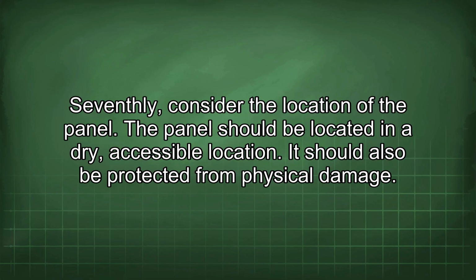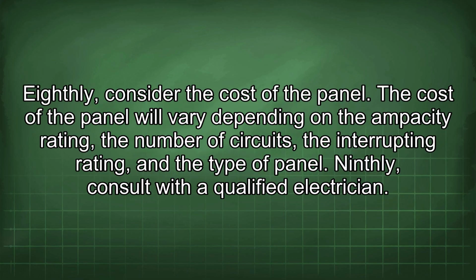Seventhly, consider the location of the panel. The panel should be located in a dry, accessible location. It should also be protected from physical damage. Eighthly, consider the cost of the panel. The cost of the panel will vary depending on the ampacity rating, the number of circuits, the interrupting rating, and the type of panel. Ninthly, consult with a qualified electrician.